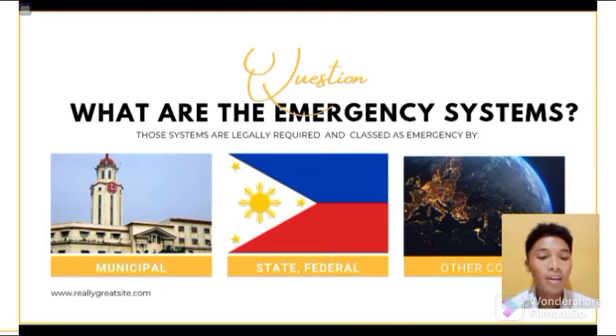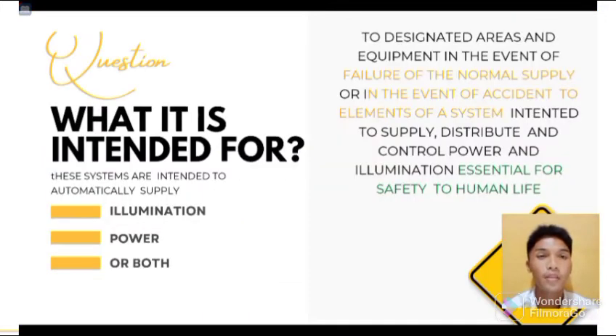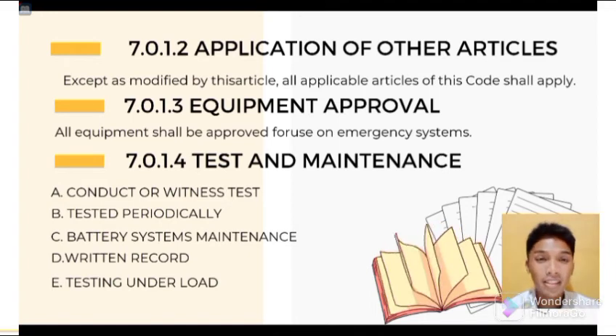So question, what are the emergency systems? Emergency systems are those systems that are legally required and classed as emergency by the municipal, state, federal, or other codes. Another question, what is it intended for? These systems are intended to automatically supply illumination, power, or both to the designated areas and equipment in the event of failure of the normal supply, or in the event of accident to the elements of a system intended to supply, distribute, and control power and illumination that is essential for the safety of human life. So the emergency systems are very important.